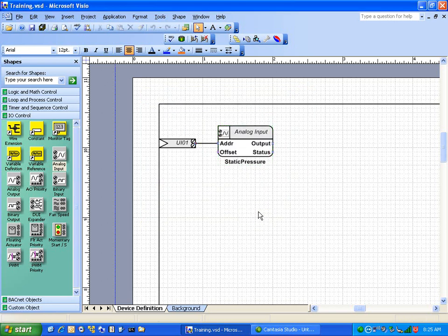You're not going to see it in the object, but we now have a COV set in this object, and we also have its engineering unit set. Very nicely, when I learn these objects up in the shadow object, all that information is going to get uploaded, which is going to be very helpful and a big time saver. Those are the important things I wanted to preach a little bit, because like I said, almost anybody can create and add an input or an output if they need to, but nobody really thoroughly completes it.